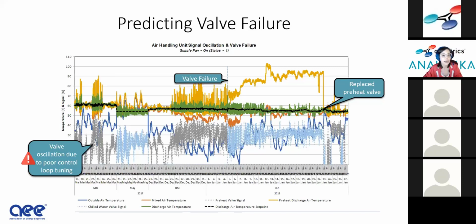So you can see this oscillation. You can see in the preheat discharge air temperature, which is yellow, it gets up to 90 degrees. It's oscillating between 90 degrees and 50 degrees back and forth. These valves are oscillating, and without analytics, you might not know it at all. You might not have any indication, because generally you're meeting your discharge air temperature set point. You can see here in January, the valve completely fails, and the preheat discharge air temperature increases well above outdoor air temperature, even though the preheat valve is signaled closed.